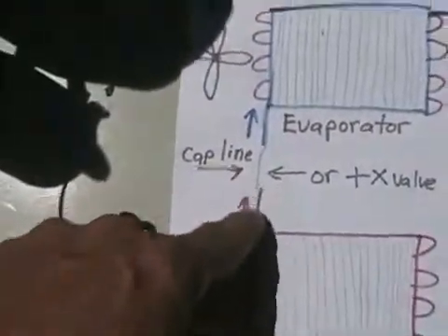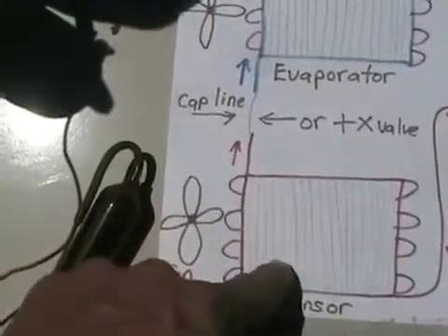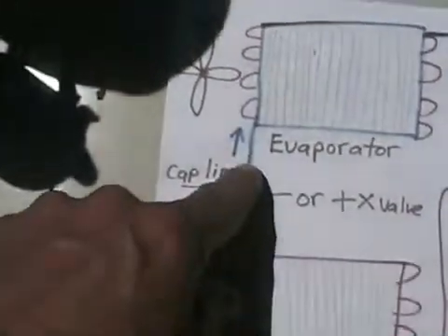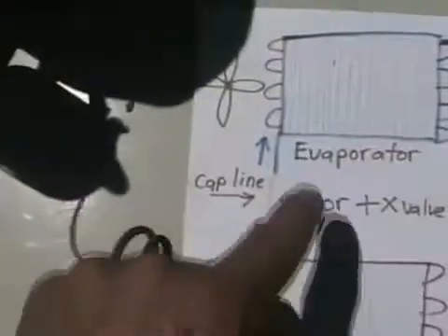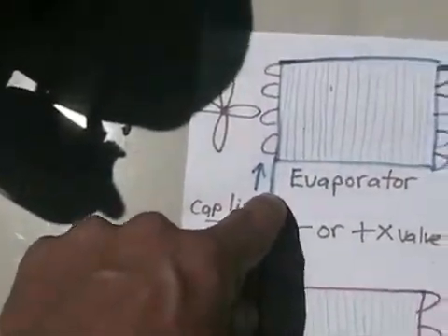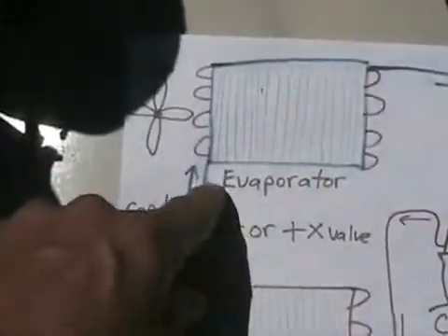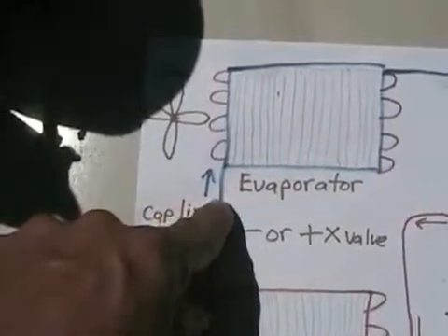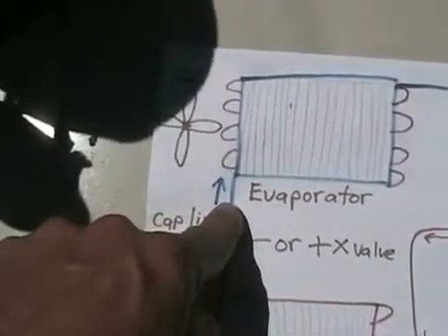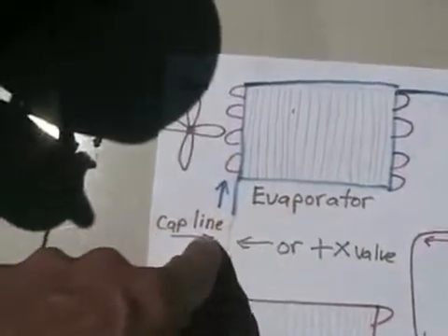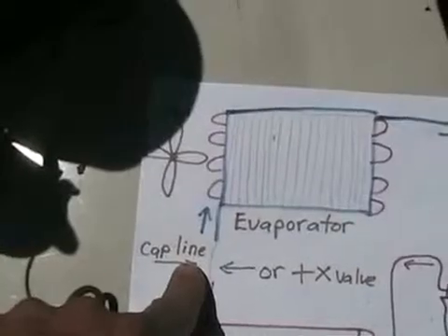The tube looks just like a wire, but it's actually hollow. The reason you have this long, skinny, restricting tube that forces the Freon through with difficulty is so that it can create back pressure, so we maintain liquid Freon on the condensing coil. By the time the Freon goes the distance of that tube and gets to the evaporator, it is in the largest diameter tubes on the air conditioner, much larger than this tube. This gives the liquid Freon some place to want to expand, and when a liquid turns to a gas, that's called evaporating, and it makes itself colder.